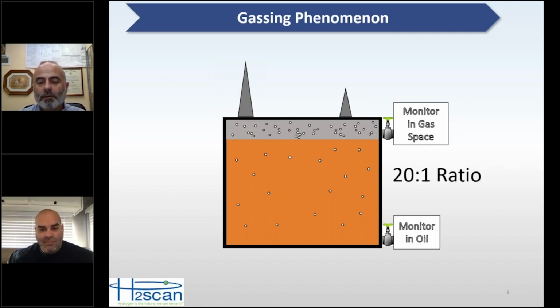And then, of course, probably 99% of the monitors today that are on transformers are monitoring in the oil. And so it's important to note, if you're measuring in the headspace, especially the hydrogen, the amount of hydrogen that dissolves in the oil, there's about a 20-to-1 ratio. So there's about 20 times more hydrogen in the gas space than there is in the oil. And so if you have a monitor that's calibrated in the headspace, you need to make sure it's calibrated at about 20 times what that monitor would be calibrated for in the oil.